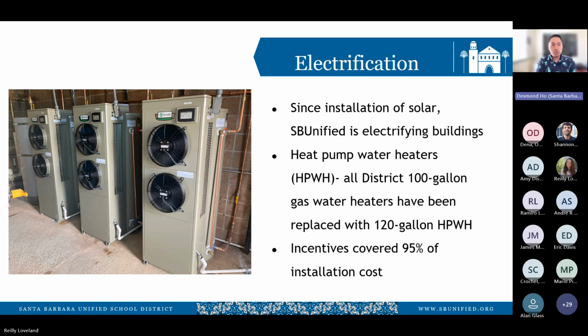Initially, we decided to go with a 2-to-1 replacement: for every 100-gallon gas water heater, we installed 2 120-gallon heat pump water heaters to make sure they could keep up with demand from kitchens and showers. However, we found that a 1-to-1 replacement was actually sufficient, provided you had a storage tank installed with it. We have approximately 40 of these installed district-wide, and the first batch were installed 3 years ago. None of them, minus one, have had any issues.